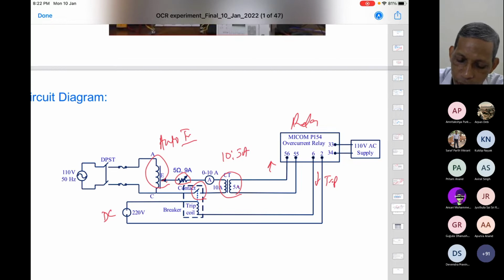This is the input current, the terminals for this case, and this is the output terminal. This relay requires power, and this power supply is 110 volt AC or DC, you can inject both. This is the overall arrangement. What you do is vary the auto transformer voltage, then the current injection through this path, a short circuit low impedance path, changes. Depending upon the voltage we apply here and the resistance setting, you can get different currents. So you inject different currents to this relay.